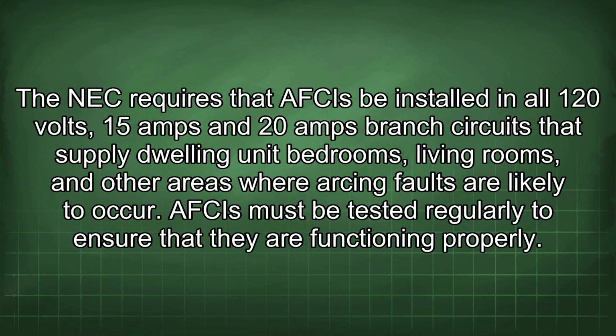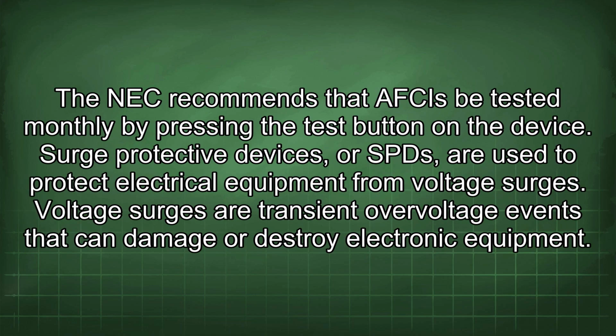The NEC requires that AFCIs be installed in all 120 volt, 15 amp and 20 amp branch circuits that supply dwelling unit bedrooms, living rooms, and other areas where arcing faults are likely to occur. AFCIs must be tested regularly to ensure that they are functioning properly. The NEC recommends that AFCIs be tested monthly by pressing the test button on the device.